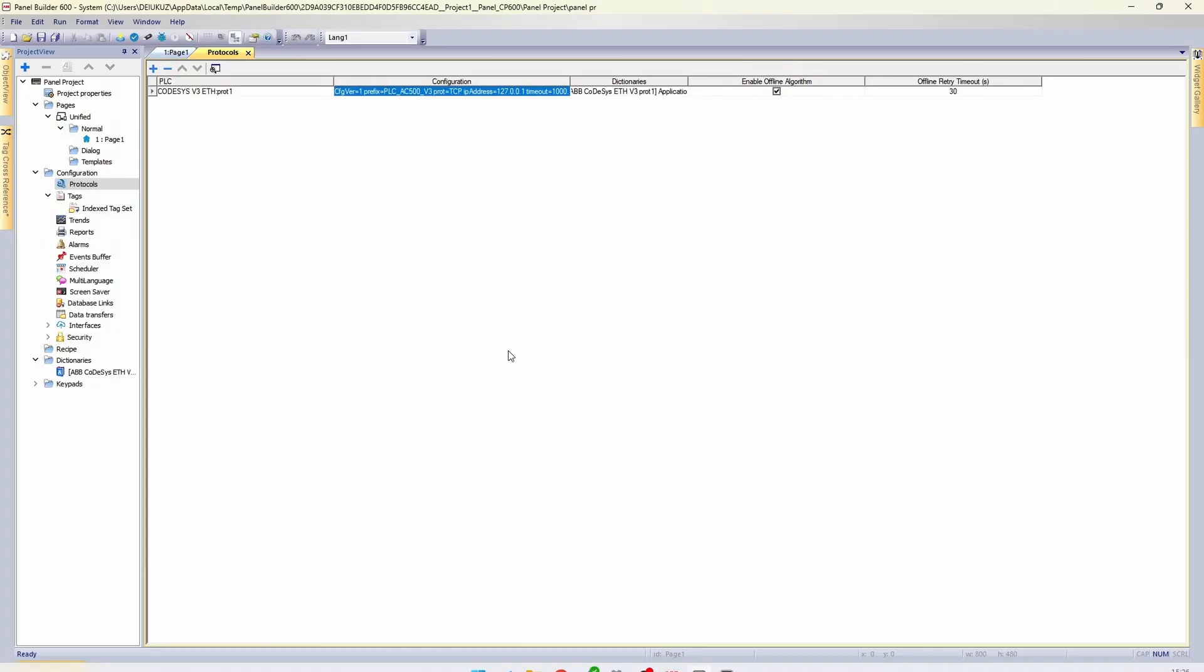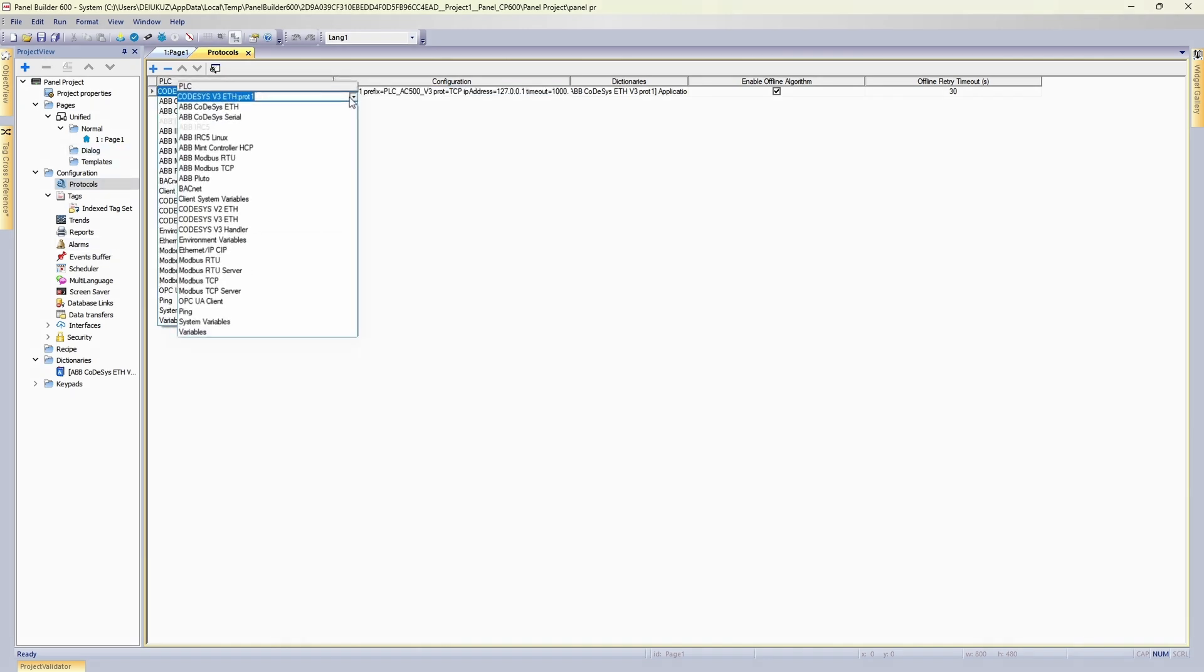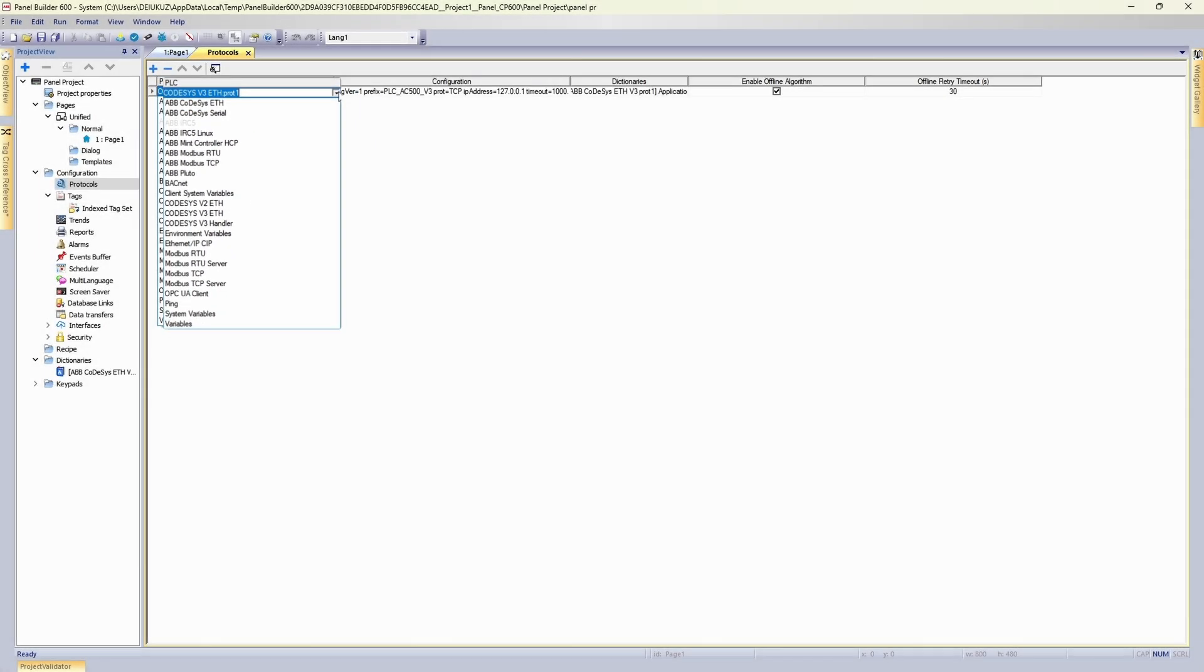But there is one caveat. Communication between two simulators will only work with either Codesys V3 ETH protocol or with Codesys V3 handler. But if you use AC500 together with CP600 panel, chances you would use one of those protocols are pretty high.